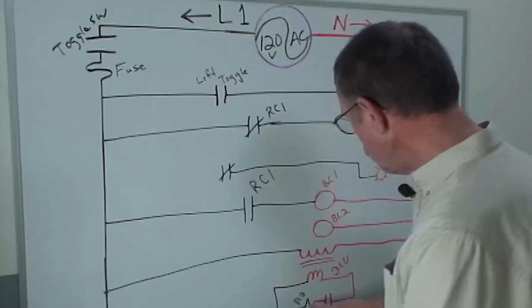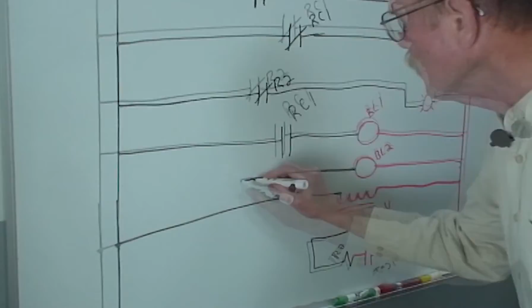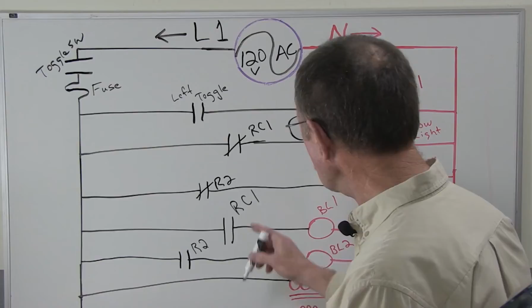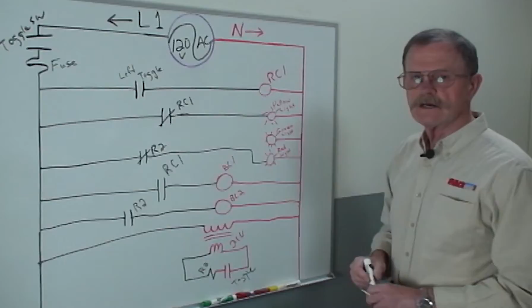Now we're going to chase out the normally open switch. And where does it go? Over here to this light, the big light. There it is, right there - big light number 2. We're on the L2 side of the load. We've already done the neutral side. It goes through a normally open switch back to L1. So I'm going to label that R2 normally open, R2 normally closed, R1 normally open, R1 normally closed. Green light, too bad - you're just there with neutral to you, but no power.